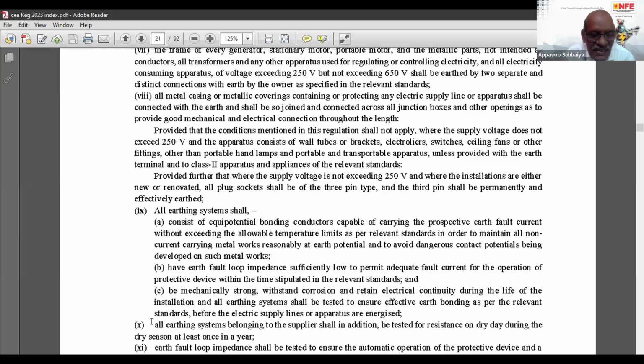So what we can infer is, while earth fault loop impedance is the responsibility of the consumer, it pertains to the consumer premises. Then there is one more regulation under 10, where the earthing system belonging to the supplier shall be tested for resistance. So we can infer that earth resistance applies to the supplier and earth fault loop impedance applies to the consumer. What we can know from regulations 18 and 43, 9 and 10, as well as 45.5, are all the things which can educate a consumer.